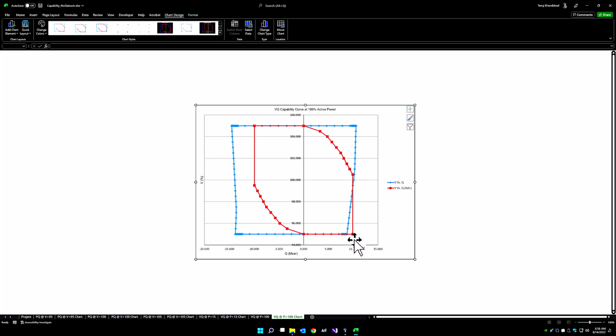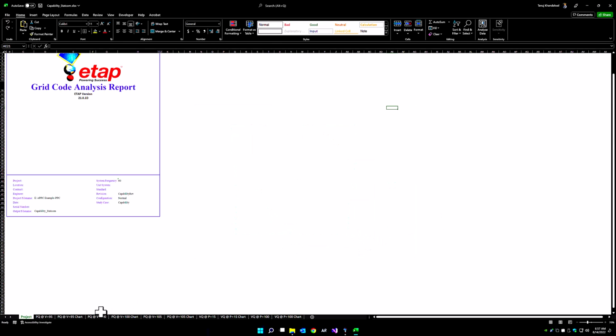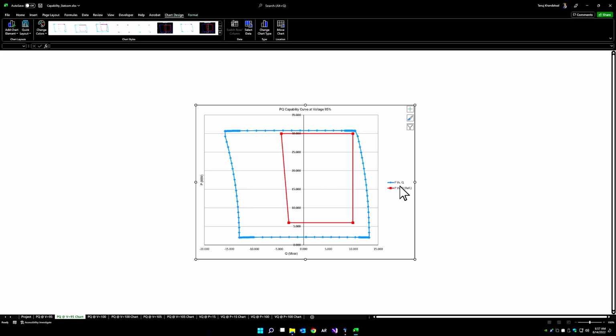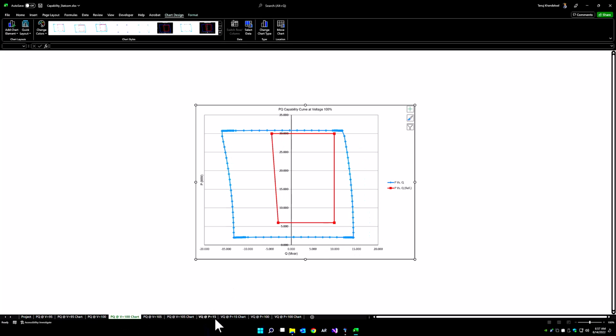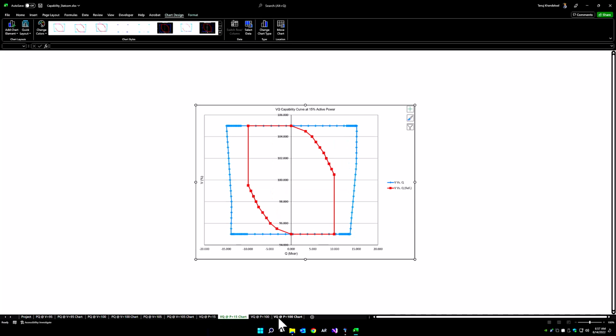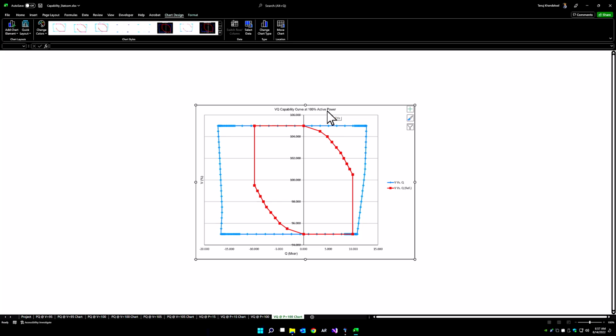And of course, the same simulation can be repeated with a STATCOM, and we can see the change in results shortly. With the STATCOM included, we can see that at 95% voltage, the STATCOM is able to bring the non-compliance region back into compliance. So the reference chart is essentially within the PQ capability of this particular site. Same thing at 100% voltage, at 105% voltage, and finally at active power of 15% and an active power of 100%. We essentially can see that there is complete compliance using a STATCOM within the system.